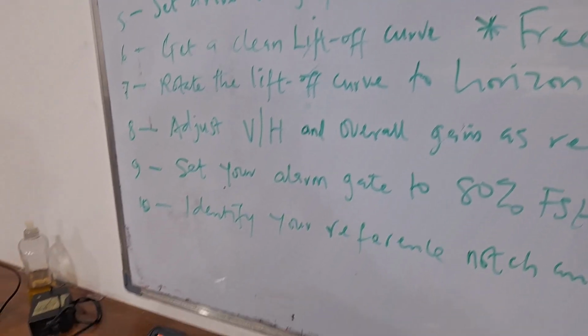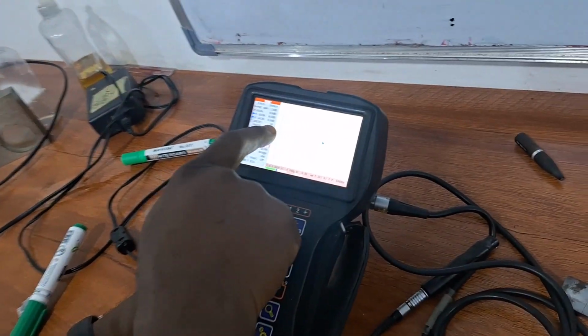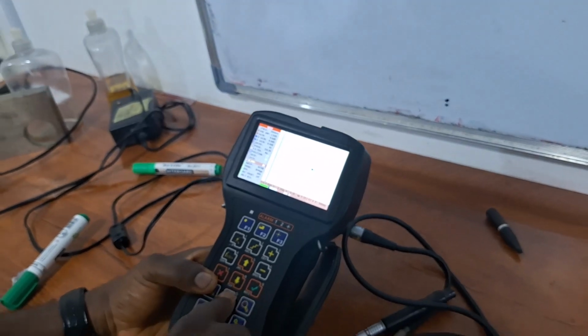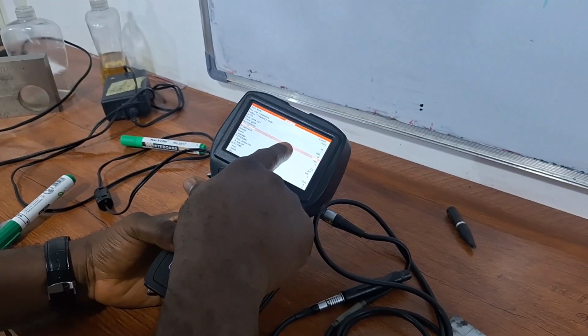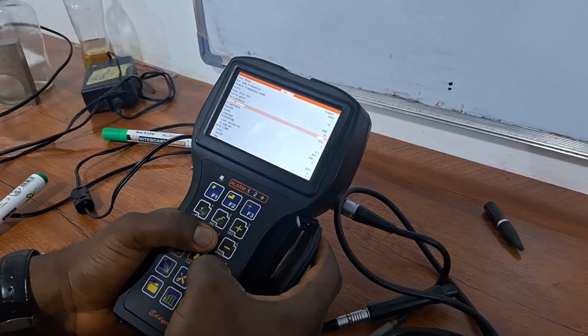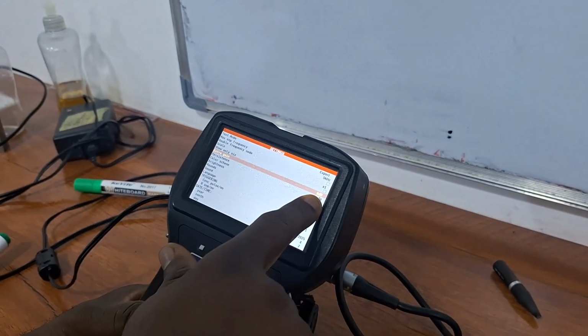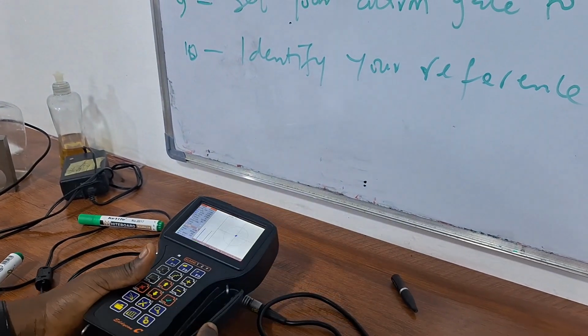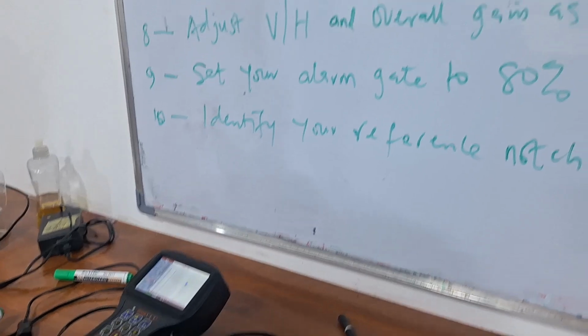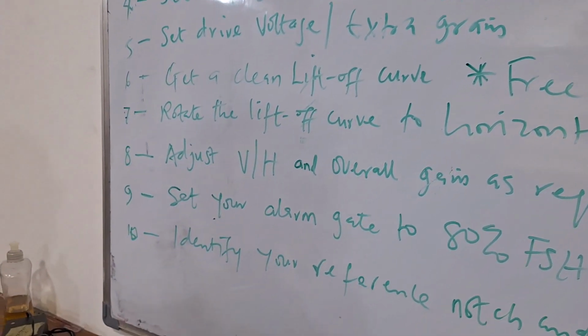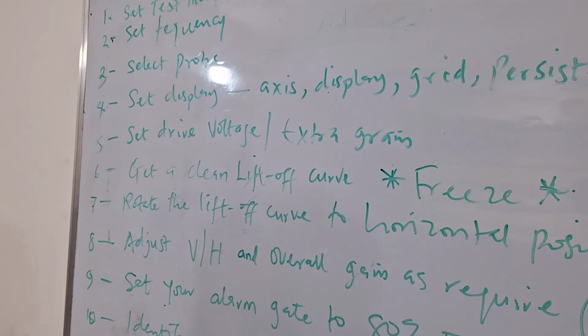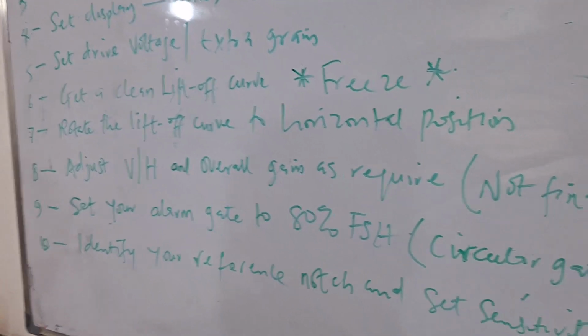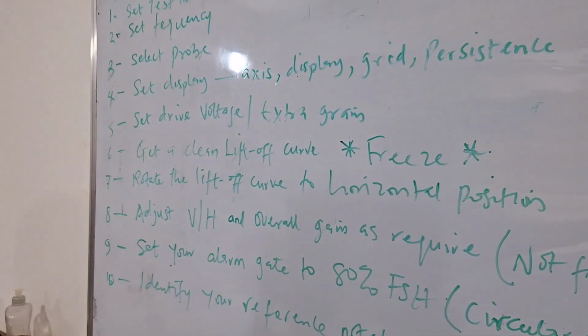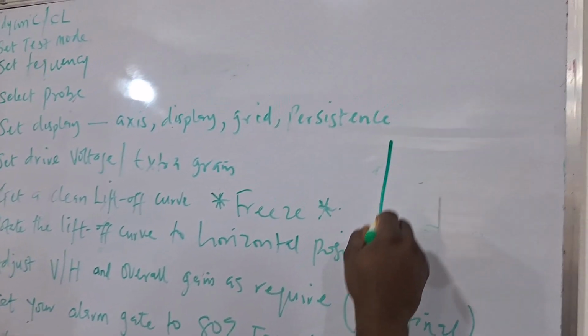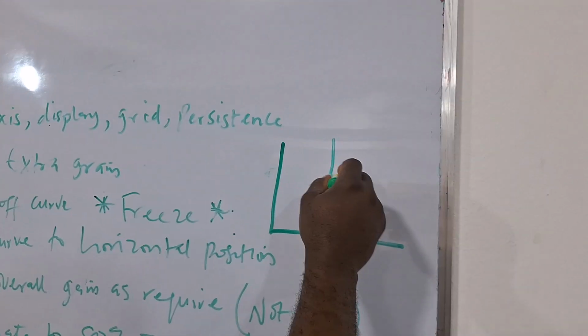So our drive voltage, I set it at 4 volts. Our extra gain from our setting, where are we? Our extra gain, I set it at 6 dB, which is the middle. So that is good enough for us. So the next part of the setup is to now find our lift-off curve. Before I proceed with this, I will just briefly talk about lift-off, though it's meant to be a topic of its own with a whole lot of explanation. But when we see the probe, this is our Eddy current probe.